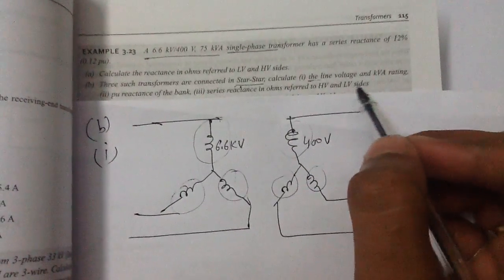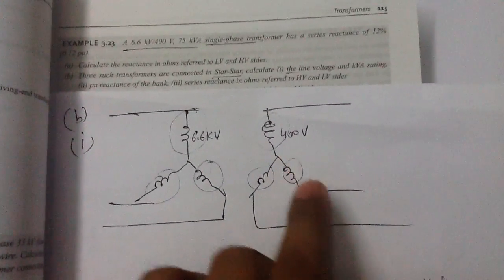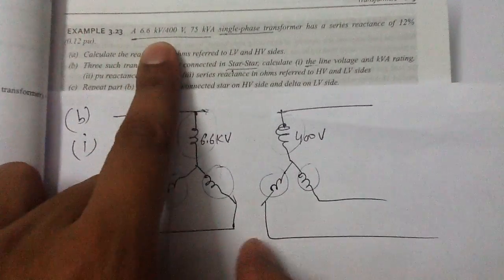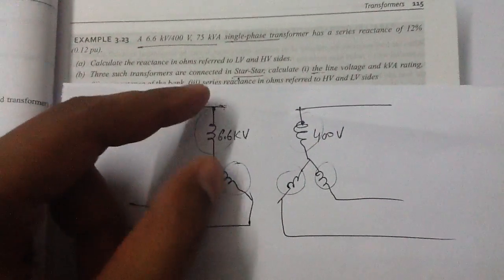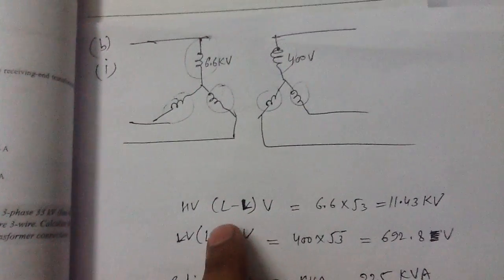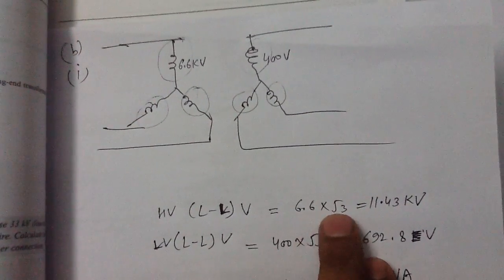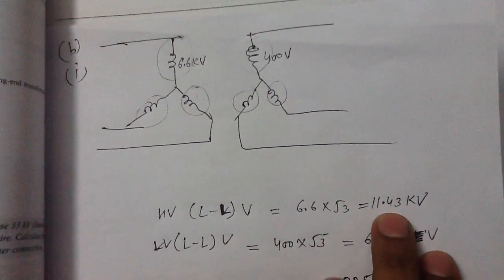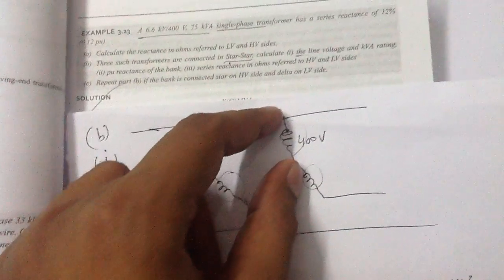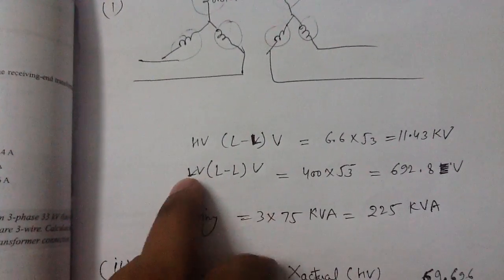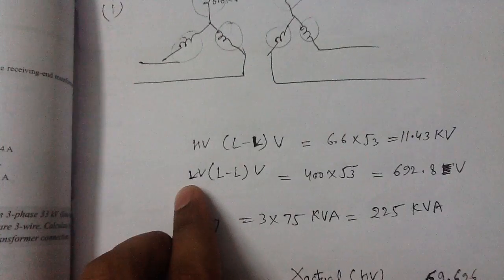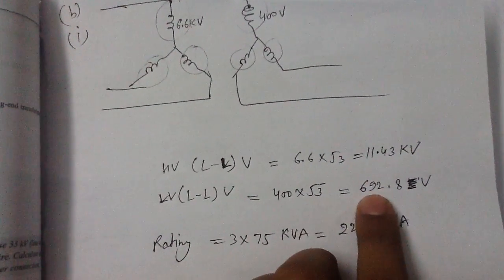Part B asks for the line voltage and the kVA rating of the whole unit. The phase voltage on the HV side is 6.6 kilovolt, so the line-to-line voltage on the HV side will be 6.6 × √3 = 11.43 kilovolt. The phase voltage on the LV side is 400 volt, so the line-to-line voltage on the LV side will be 400 × √3 = 692.8 volt.